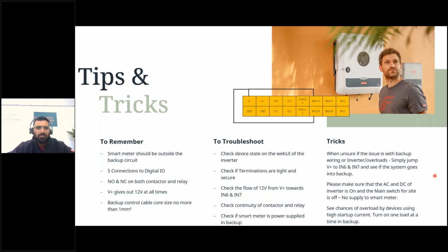Also, another thing to keep in mind, I would recommend using a CAT cable. But if you are using an instrumentation cable or something else, it is not recommended to use anything which is more than 1 millimeter square thickness. So what can we do to troubleshoot the system in case the backup is not working?